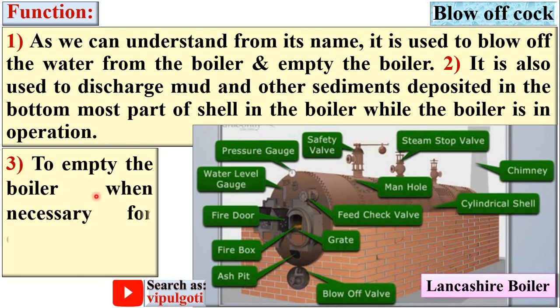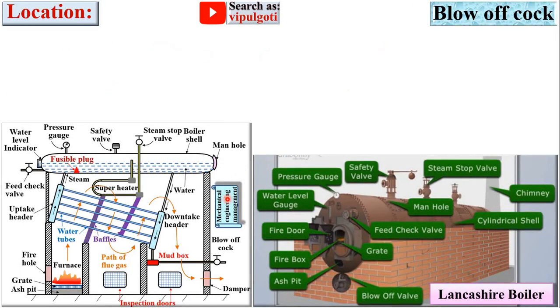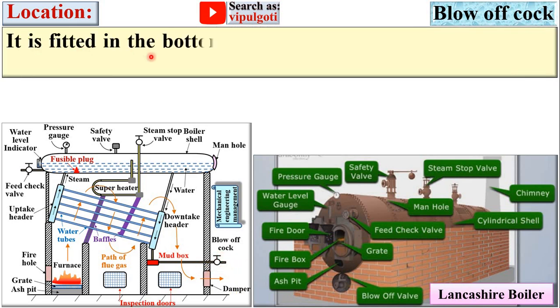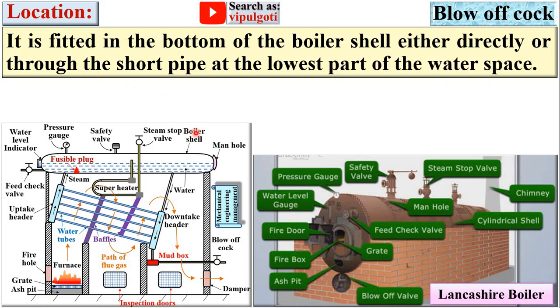The third function is to empty the boiler when necessary for cleaning, repair, and inspection. Now, the location of the blow-off cock: in this Babcock and Wilcox boiler, you can see it is fitted at the bottom of the boiler shell, either directly or through a short pipe, at the lowest part of the water space.